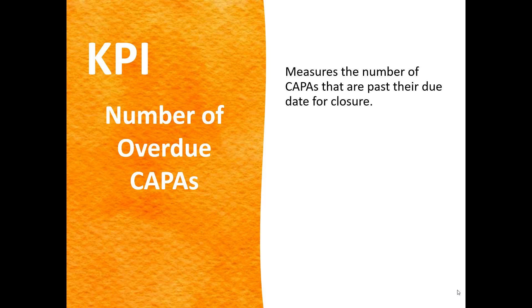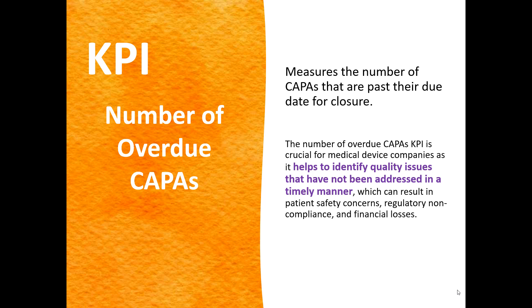Another KPI could be the tracking number of overdue CAPAs. When you open a CAPA, you should set a closure date for it — you need to ensure you know when you want to have the CAPA closed by. You should view CAPAs as mini projects: if you start a project, you need a start date and a proposed end date. Therefore, you should also be tracking CAPAs that pass their due date. If you have a lot of overdue CAPAs, that would be very concerning. A company should action those overdue CAPAs and give them more resources to ensure they are closed out quickly.